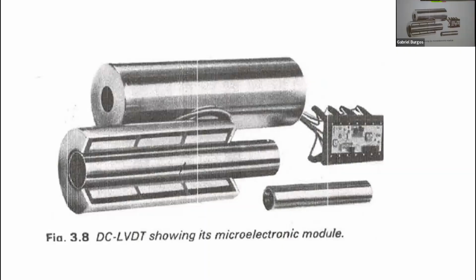It has all the same features, but it has two limitations. One is the temperature limitation of the electronics, at most 125 C. The second limitation is that the DC outputs from DC LVDTs are relatively limited. You don't get a chance to make the output variable, higher or lower.